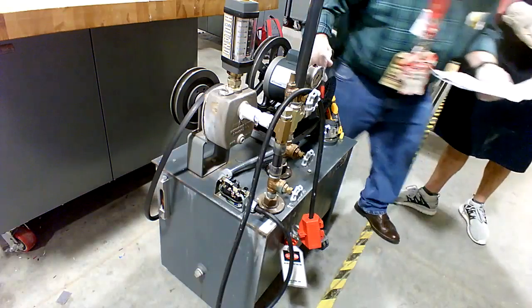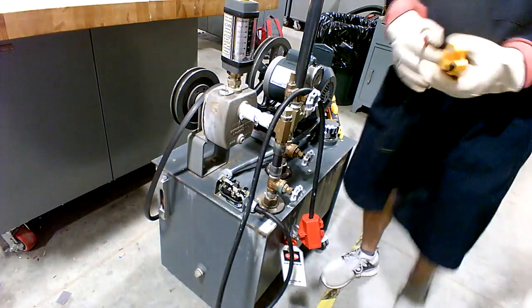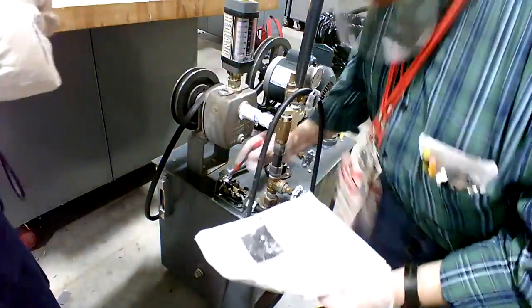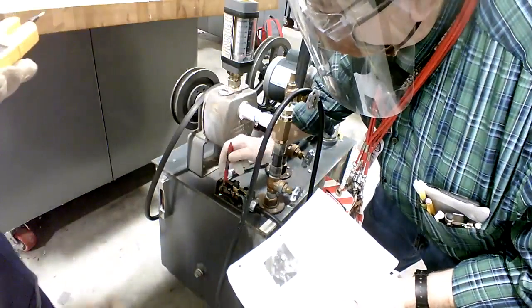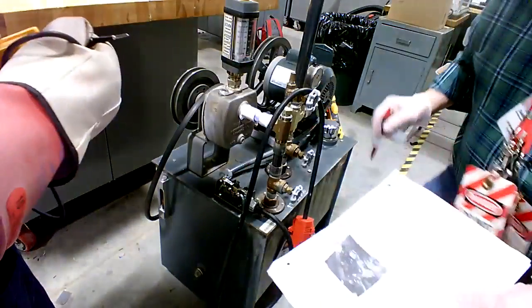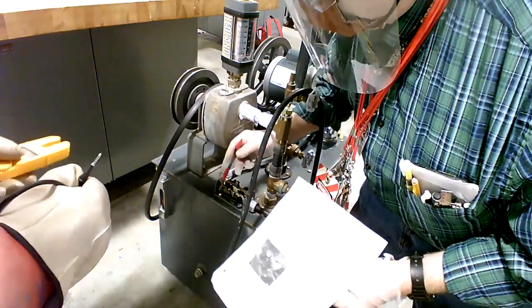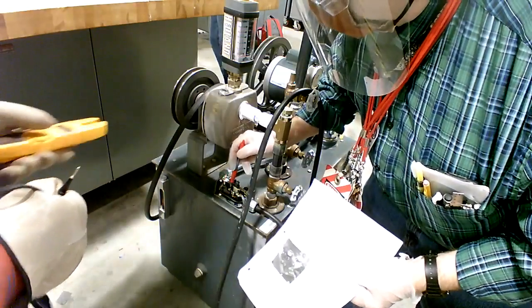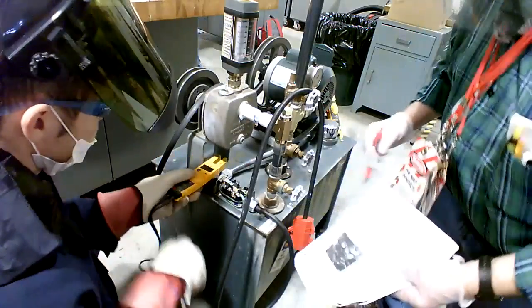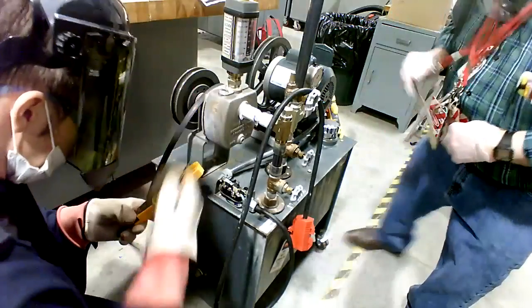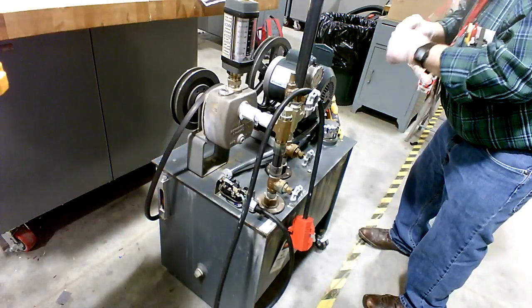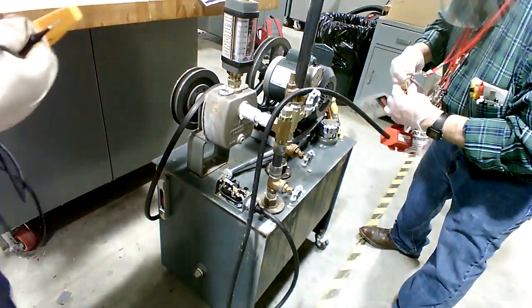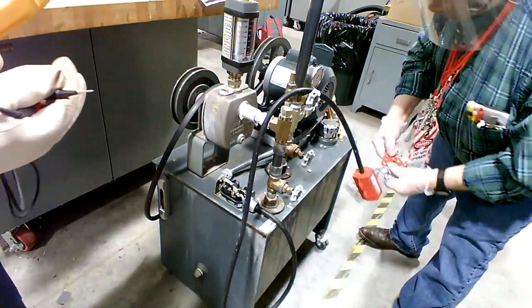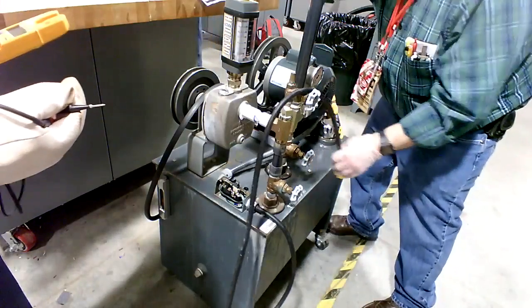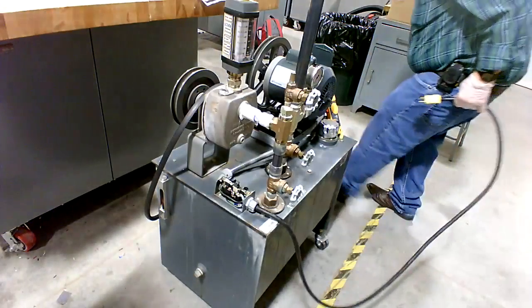Keep the motor ground. So I want you to come out here with the meter. When I plug this in, I want you to go with that meter and touch here and touch ground at the same time. So put the red probe there, the black probe down there. And then I want you to keep the black probe on ground and move that red one from here and put it here. You'll see that it won't be on here, but it will be here, because the switch isn't on yet. So yeah, bring your face shield down. Now that 1.4, we got that.